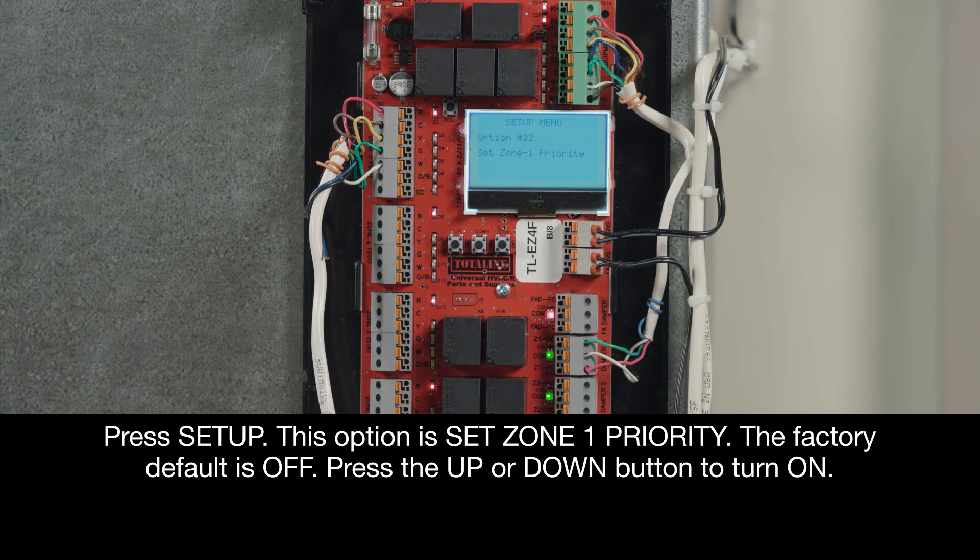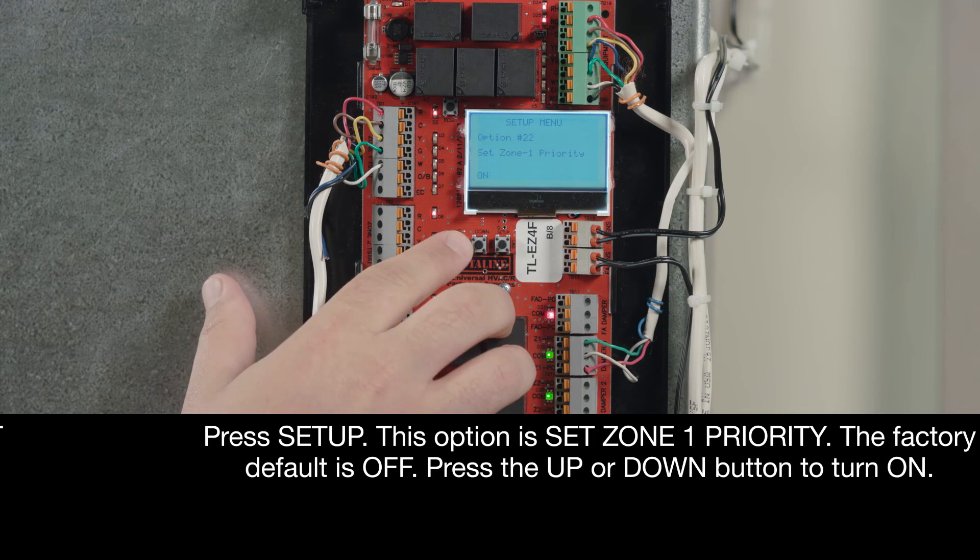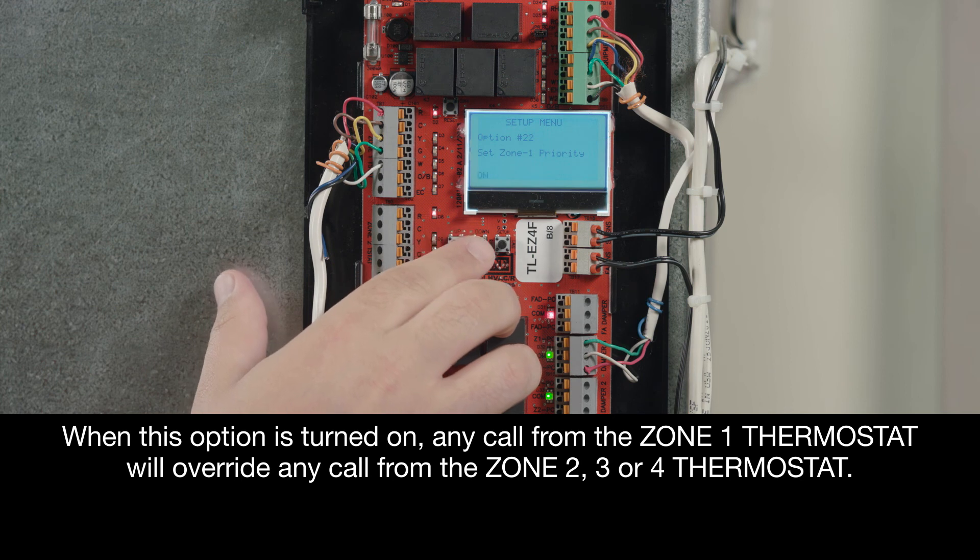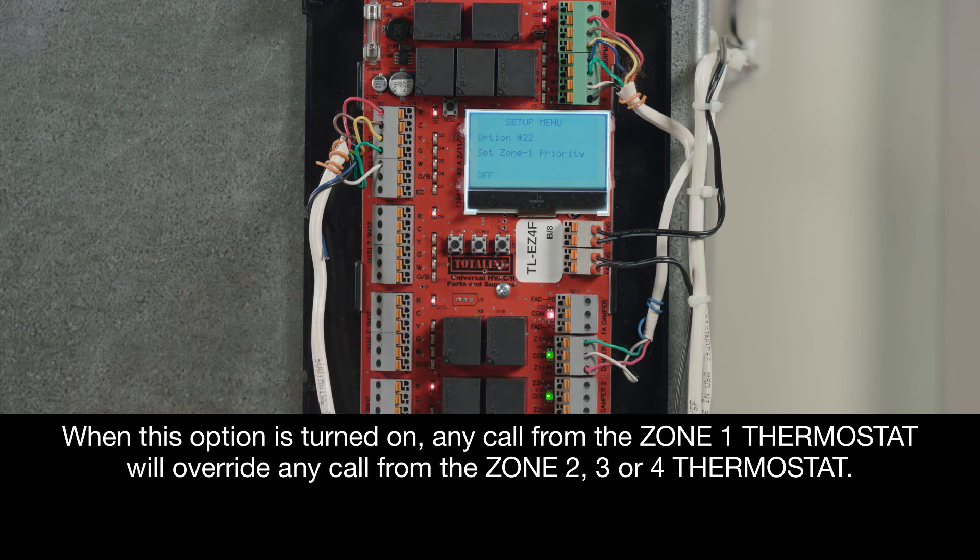This option is Set Zone 1 priority. The factory default is OFF. Press the Up or Down button to turn ON. When this option is turned ON, any call from the Zone 1 thermostat will override any call from the Zone 2, 3, or 4 thermostat.